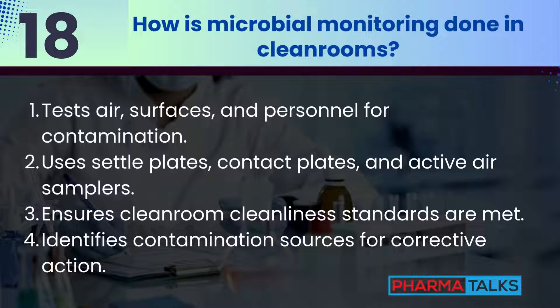How is microbial monitoring done in clean rooms? Microbial monitoring involves testing air, surfaces, and personnel for contamination. Methods include settle plates, contact plates, and active air samplers. Regular monitoring ensures the environment meets cleanliness standards. It also identifies contamination sources for corrective action.